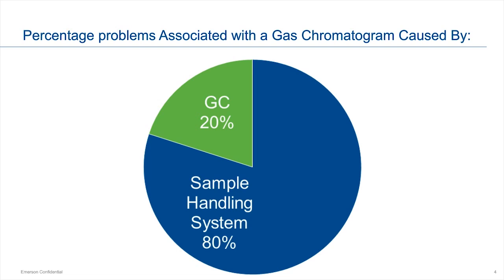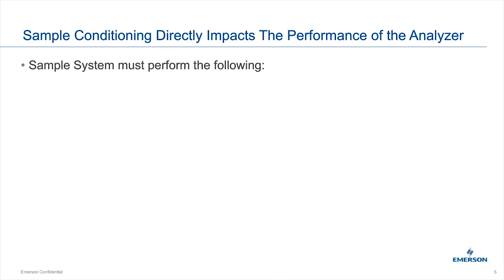What exactly is the purpose of a sample handling system? It has five functions. First, it needs to take a representative sample — whatever is flowing in the pipe is what you need to pull out and send to the GC. The GC gives very accurate results; it will analyze exactly what you give it. If you don't give it what's actually in the pipe, you won't get an accurate analysis of what you're looking for.